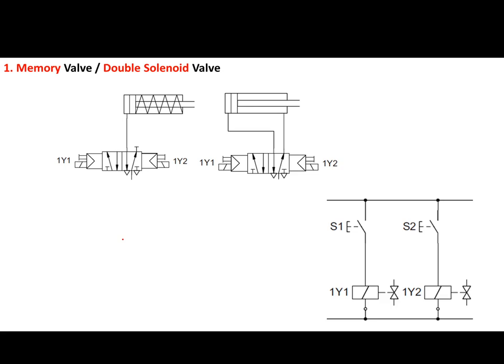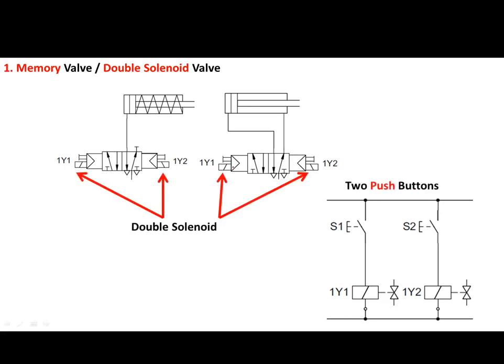The first method uses a double solenoid valve with two push buttons. The double solenoid valve is what makes the signal storage possible, and it doesn't matter whether it is a single-acting or double-acting cylinder. Once one solenoid is energized, the DCV will be in the left switching position, and it maintains that position until the next signal is sent. To achieve this electrically, we need one push button for each solenoid.